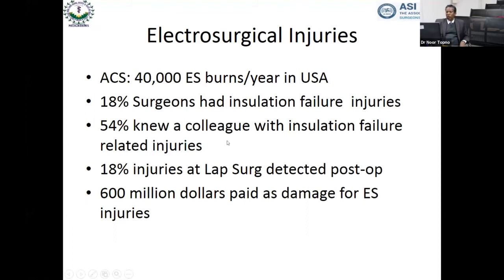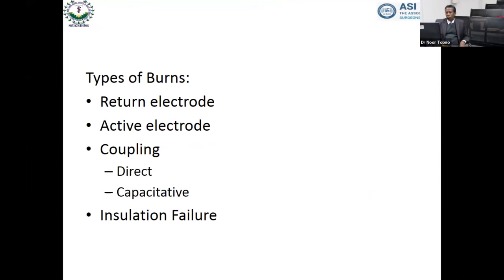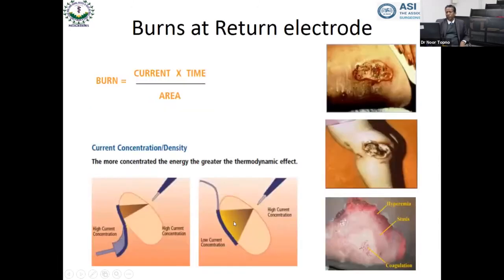Just to touch upon how important electrosurgical units are vis-a-vis injuries, the American College of Surgeons has reported almost 40,000 surgical burns per year. And 18% of surgeons had insulation failure. This is pertaining to usually laparoscopic surgery. And 54% knew a colleague who had insulation failure. The sum total paid as compensation for these injuries was about $60 million. Now, when you talk about burns, there are typically 4 types. One happens at the return electrode, number 2 at the active electrode, then there is something called coupling, which is direct and capacitive, and the 4th variety is insulation failure.